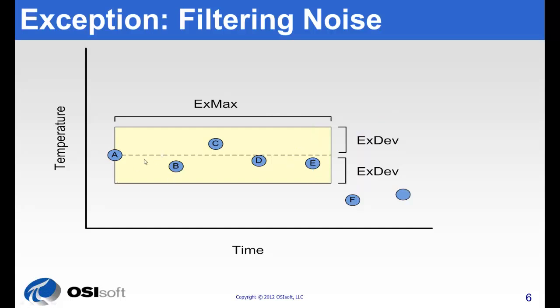The PI tag attributes that define exception are exception max, which defines the length of time we'll go before we, for sure, report a value, and exception deviation, which defines the width of this dead band.